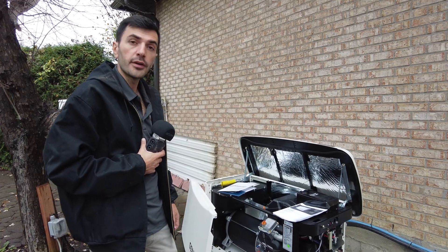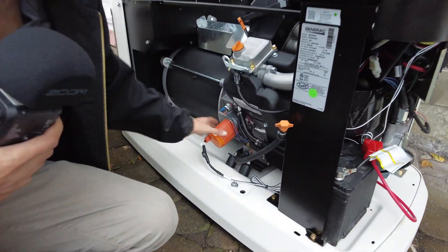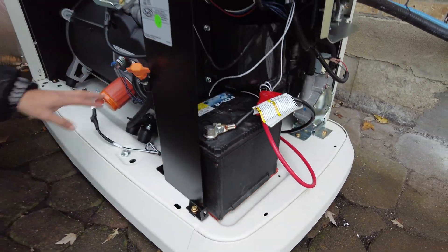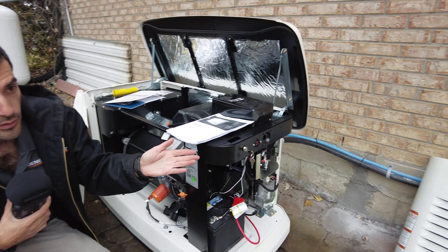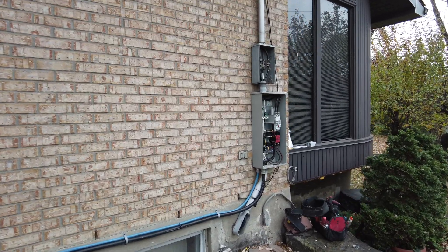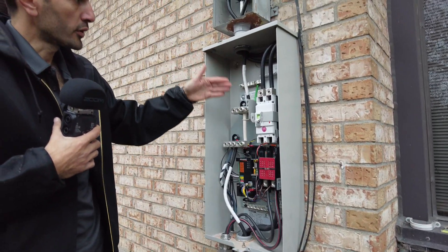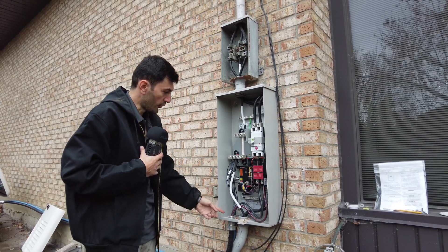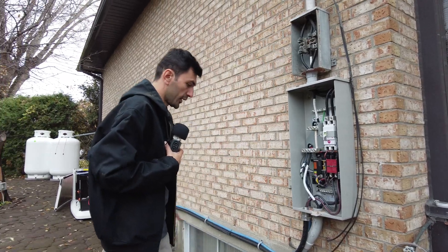The warmers I mentioned earlier — this one is for the oil and this one is for the battery underneath, to keep the battery and oil warm in winter so the generator starts easily. If you compare visually, you will see how the wires are fixed and how the transfer switch is mounted — it's different. The connectors are not under pressure, the wires are not under pressure, it's nice and clean. The top compartment is isolated from the bottom — on the other installation it was not. This is the way it has to be installed.